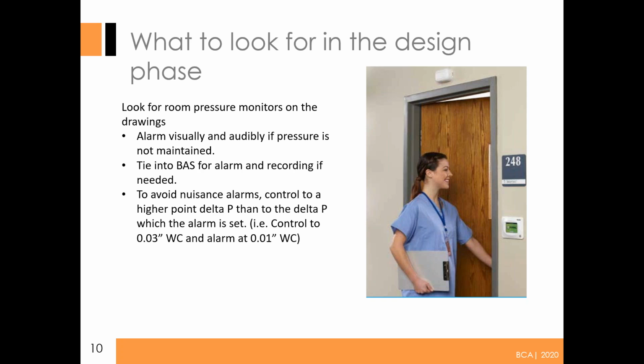And then to avoid the nuisance alarms, always suggest that you control to a higher point than the alarm set. So for instance, if the alarm is going to be set at 0.01, then control to 0.03, and then the fluctuations will maybe drop it down to 0.02, and you won't be getting these nuisance alarms. And that goes for any type of room. Always be a little bit above it, but not too crazy above it.